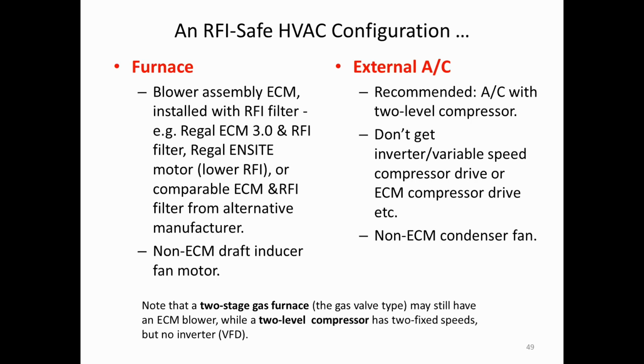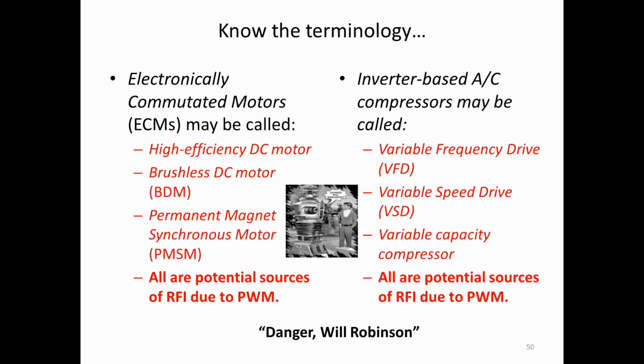Also, be careful about the terminology. You'll notice that a 2-stage gas furnace can still have an ECM blower. A 2-stage gas furnace has a burner which has a high flame and a low flame. But a 2-level compressor has 2 fixed speeds and no inverter. Here again, just know the terminology. ECMs can be called high efficiency DC motors, BDMs, PMSMs. Inverter-based AC compressors can be referred to as VFDs, VSDs, variable capacity compressors. It took me a while to learn the jargon just so I could talk to the field engineers.